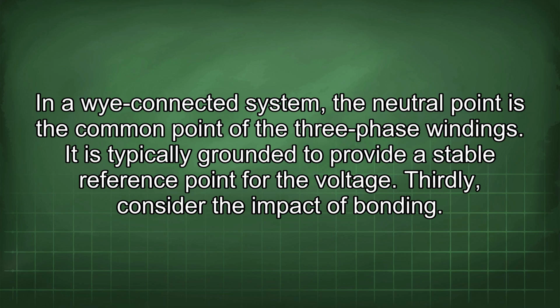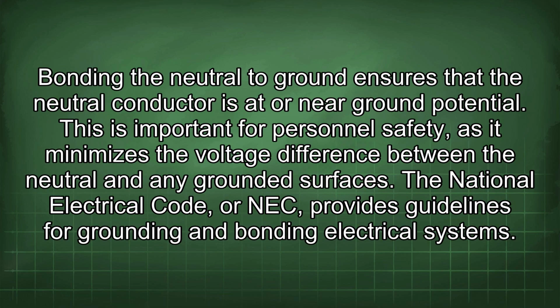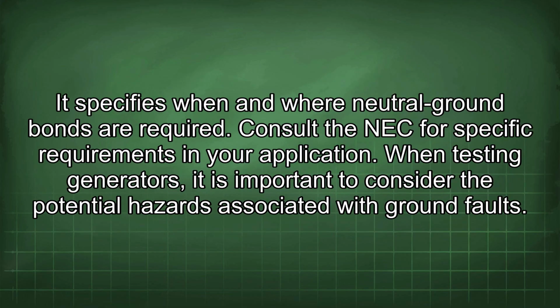Thirdly, consider the impact of bonding. Bonding the neutral to ground ensures that the neutral conductor is at or near ground potential. This is important for personnel safety, as it minimizes the voltage difference between the neutral and any grounded surfaces. The National Electrical Code, or NEC, provides guidelines for grounding and bonding electrical systems. It specifies when and where neutral ground bonds are required. Consult the NEC for specific requirements in your application.